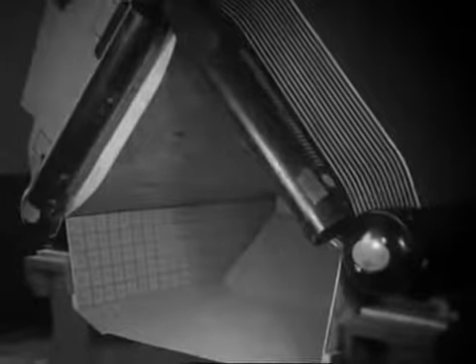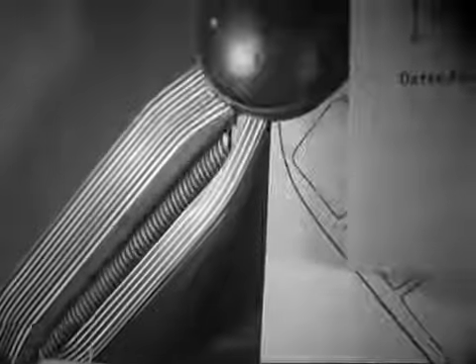This model boiler with casings on one side removed gives us a perfectly clear idea of the superheater layout. Its tubes, remote from water, are a unit on their own, running between the boiler tubes for their full length and depth. Engine efficiency depends upon limits of temperature, high when the steam enters, low when it leaves, hence superheating, which raises temperature without pressure increase and saves fuel, for less steam is required and, being dry, causes no corrosion.